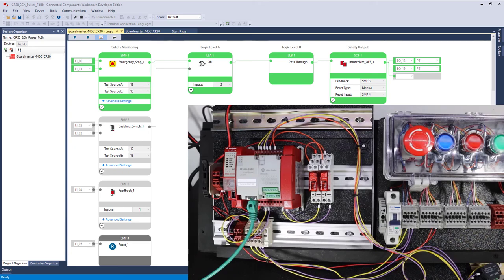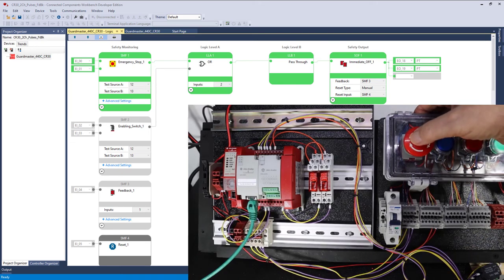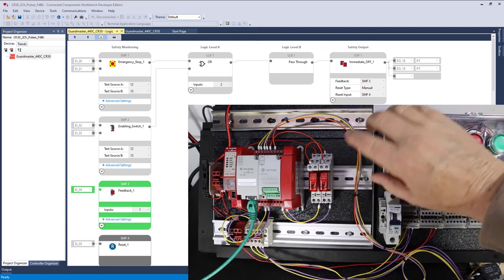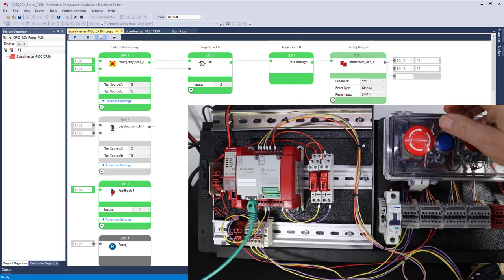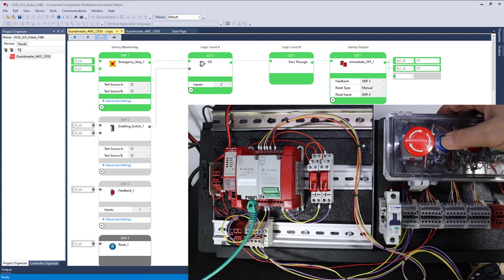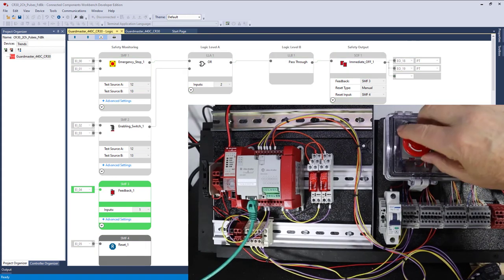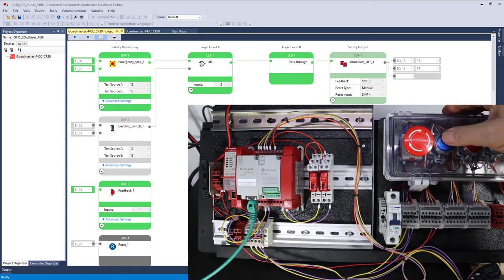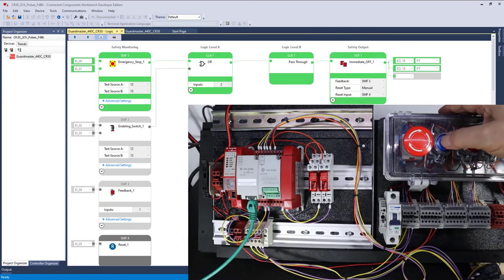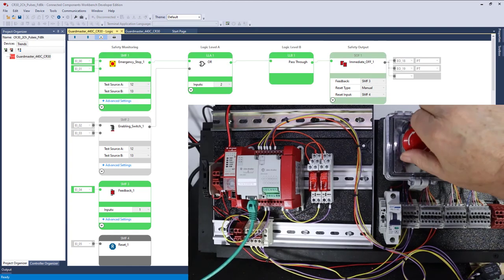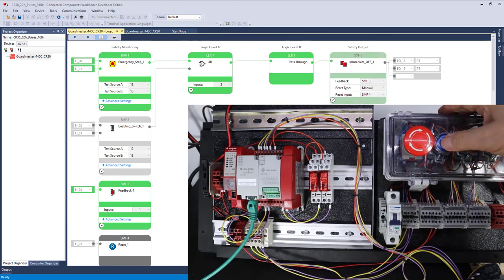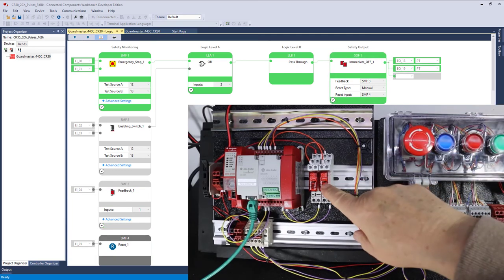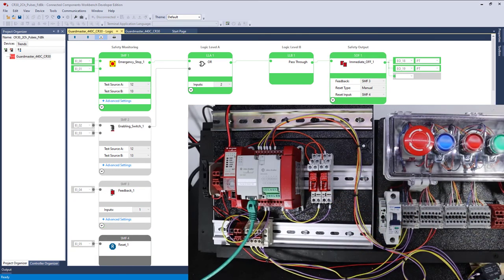Push the e-stop. E-stop. See these went off. Reset it. It didn't reset. Push the reset button. And it's reset. E-stop. Doesn't reset it. Reset button. Notice that it resets it when I release it. So release that. It doesn't reset. Push it in. It does not reset. But when I release it, then it resets. Real simple.